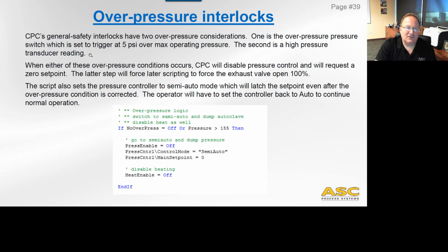Okay. Overpressure interlocks. Okay, CPC's general safety interlocks have two overpressure conditions. One is the overpressure pressure switch, which is generally set to trigger about 5 psi over maximum operating pressure. And the second is the high pressure transducer reading, or the pressure transducer reading which might be high. So when either of these overpressure conditions occurs, we want CPC to disable pressure control and request a zero set point. The latter step will force later scripting to force the exhaust valve open. We just talked about that in the pressure section. So the script also sets the pressure controller to semi-auto. So this is a little bit different than the temperature one.